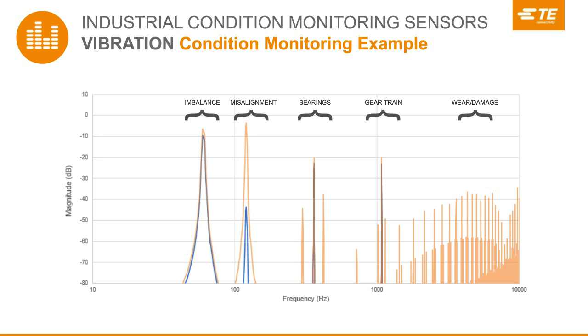When wear occurs, we often see modulation effects or sidebands appearing around the bearing and the gear frequencies. Damage to bearings or gear teeth tends to be associated with discontinuities in displacement. And because acceleration is the second derivative of displacement, this results in whole families of higher harmonic components and a general increase in the high frequency noise in the acceleration domain. This is why accelerometers are particularly useful in condition monitoring. The early detection of these changes in the high frequency signals is key to predictive maintenance. With some prior knowledge of the machine, we can assess the extent of the wear or the type of defects occurring and predict when maintenance should be scheduled.